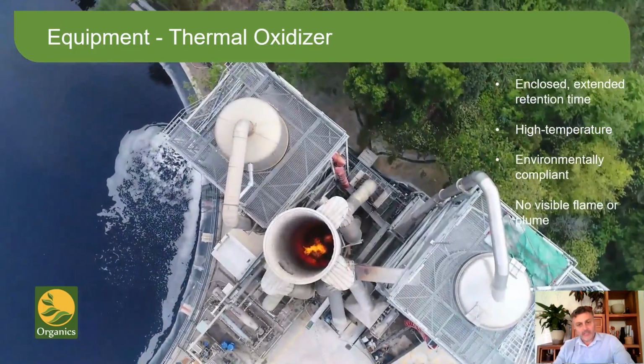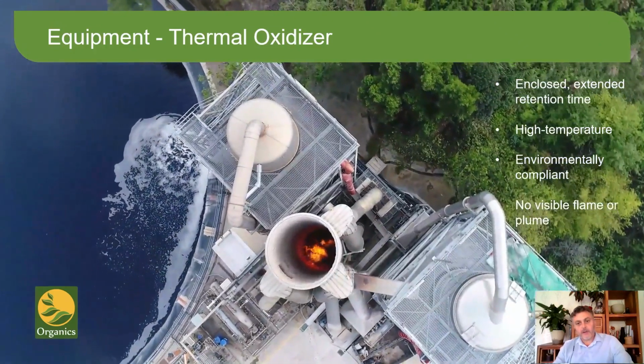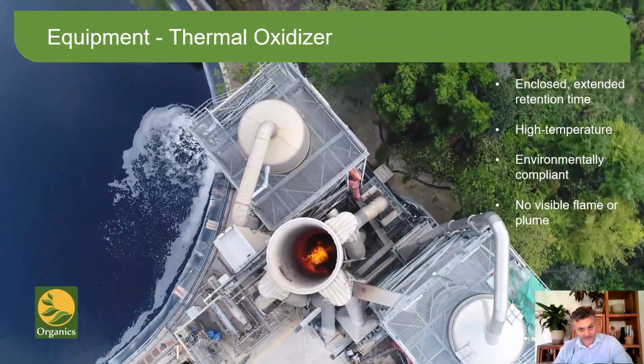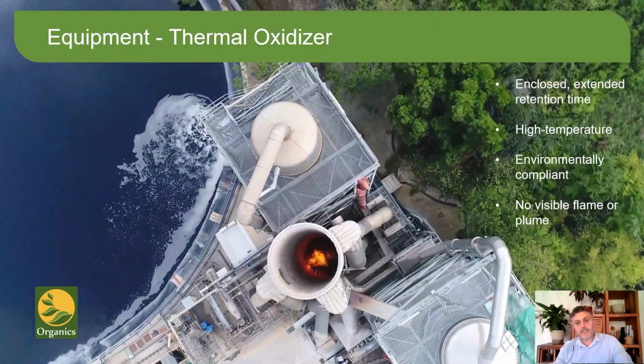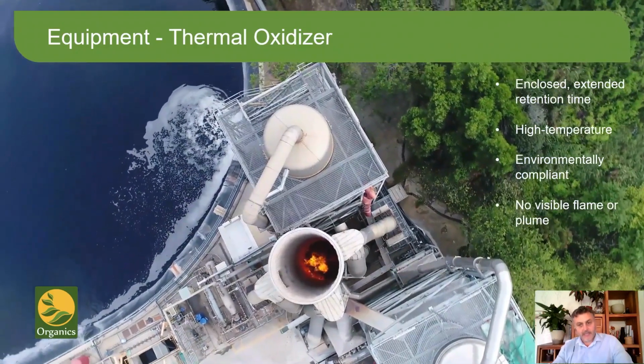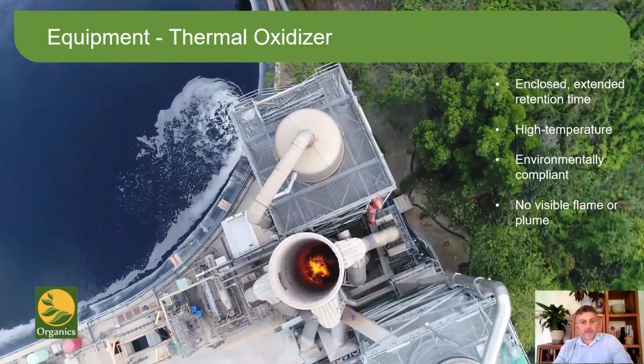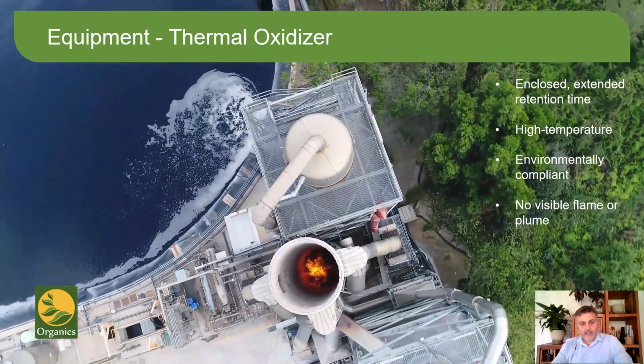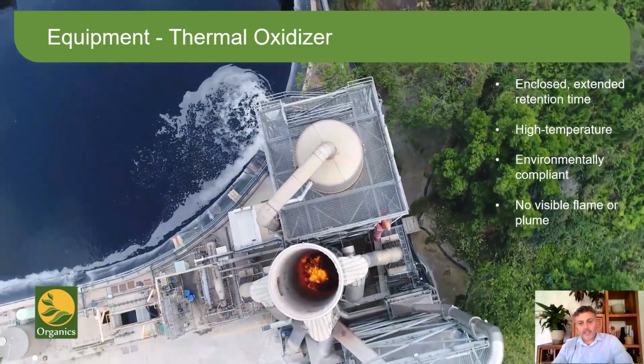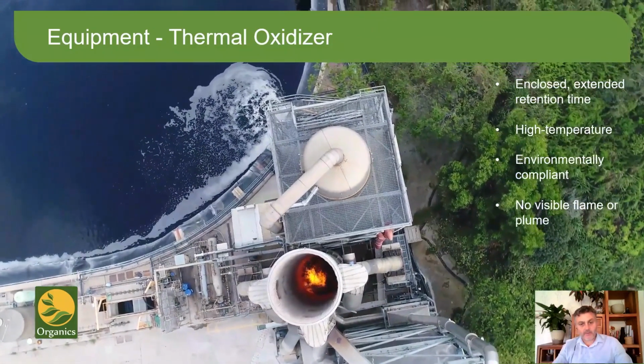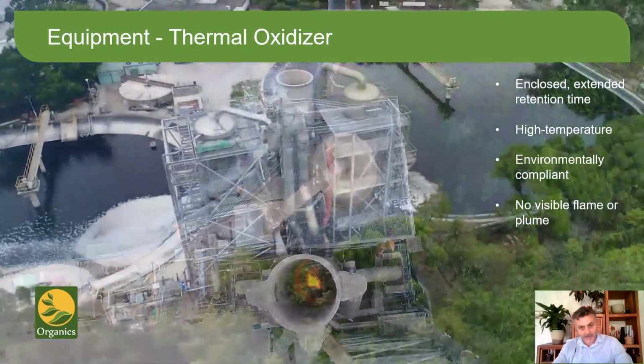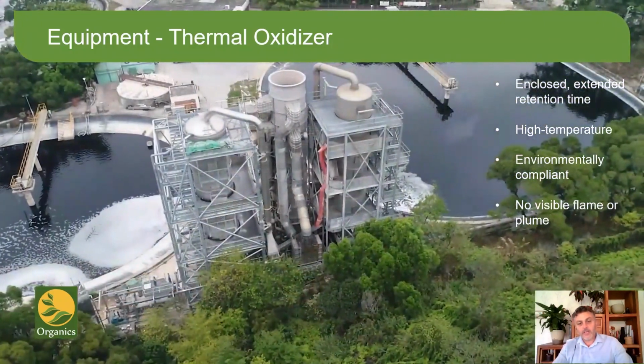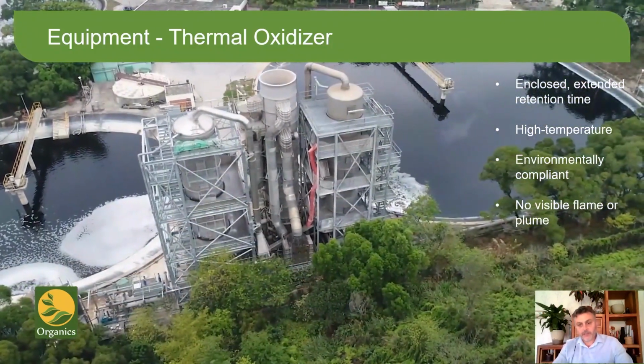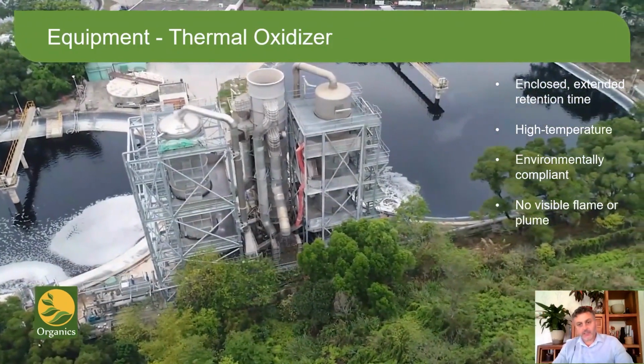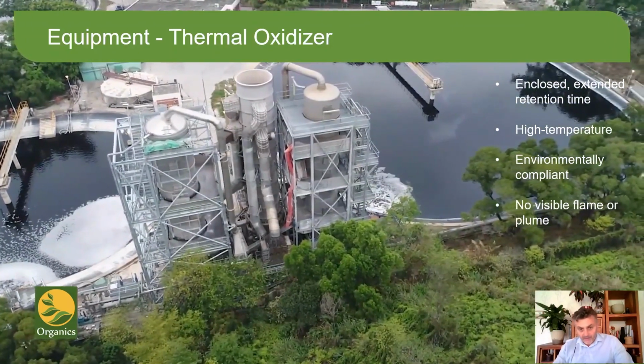We'll have a little look at those features later on, but for now the important aspect of these combustors is that they are both combusting a fuel gas, in the case of landfill gas, and combusting and destroying the ammonia. The heat generated is then used to provide the energy for the process. Like all our ground flares, these thermal destructors are fully enclosed to provide a closed environment where we can guarantee that the waste gases are exposed to a known temperature for a known time. This is the retention time and is what drives the height of the units.